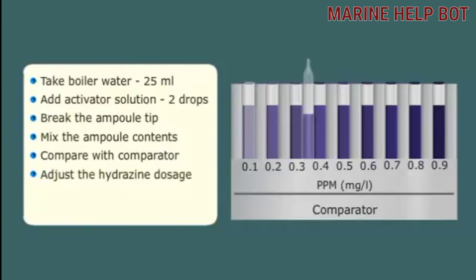Adjust hydrazine dosage to the boiler water so that hydrazine reserve is maintained between 0.1 to 1 parts per million.